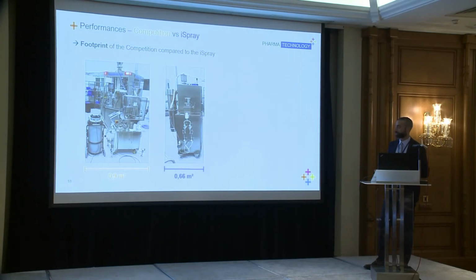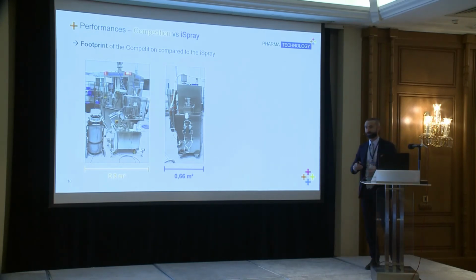That's the iSpray version for single side — backup line as well, single side press with on-board aspiration. There is also a pneumatic valve, so the machine doesn't have to be stopped when the reservoir of the magnesium stearate vacuum bag is full. It automatically closes the valve, the operator changes it, puts it back in place, and you start again.